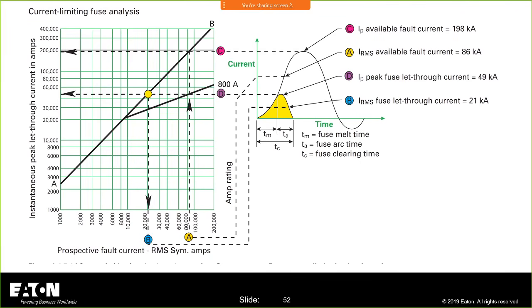Also non-current limiting. Oh, okay. So other manufacturers may have K5 fuses that are non-current limiting. That's true. If I have a high short circuit value and I need to reduce the short circuit current, can I use a current limiting fuse and it will reduce the value without damage? So yes, you can. If you take a look at this whole discussion that we just had on the current let-through, the RMS values, I am able to reduce the RMS, but again, it's how you're going to use it.